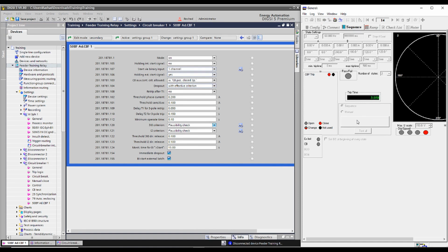So now as a supervisor, I'm telling you that I'm going to remove the binary input of the breaker being closed. All right, I've removed the binary input of the breaker being closed. What happened? The function reset. Why? Because the function operated through initiation with the breaker condition. All right, stop and reconnect the input again.